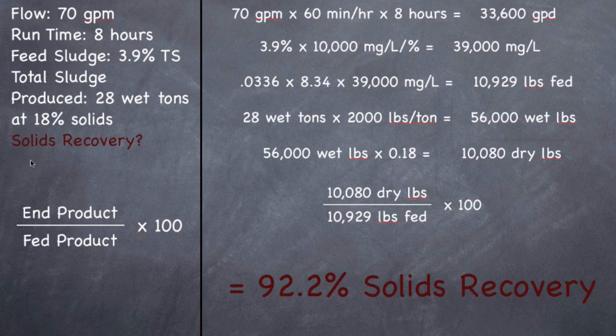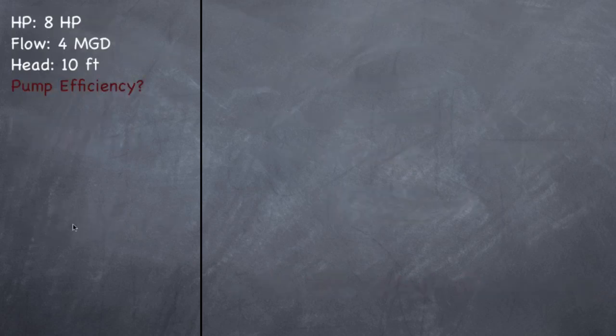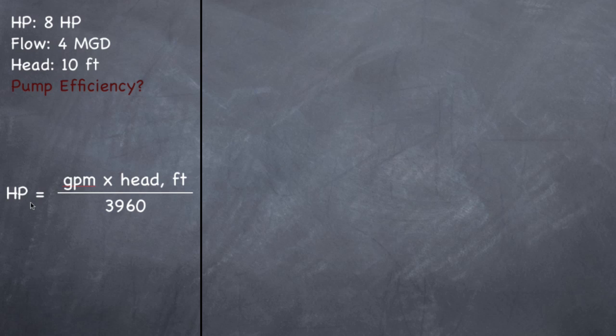And that's solids recovery for a belt press. Last problem: pump efficiency. We have an 8 horsepower pump pumping 4 MGD against 10 feet of head — it's pushing water up 10 feet. They want to know how efficient this pump is. There are two formulas: to find horsepower, you need gallons per minute times head in feet divided by 3960.